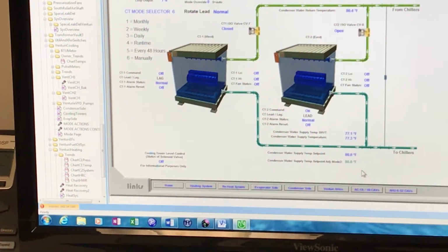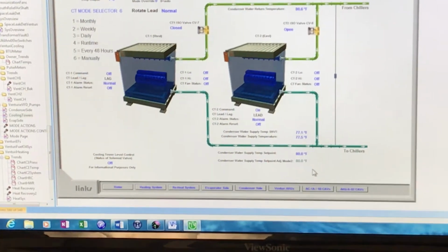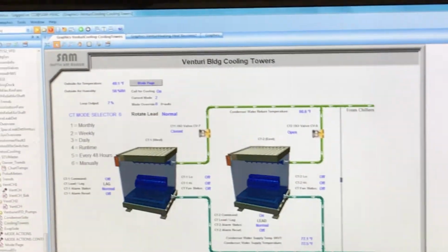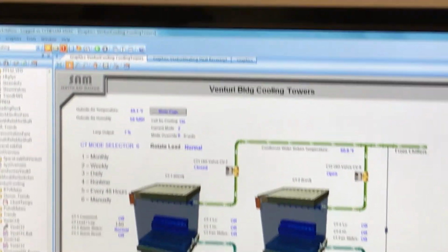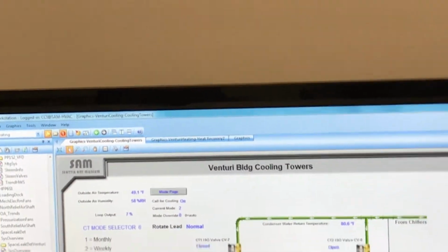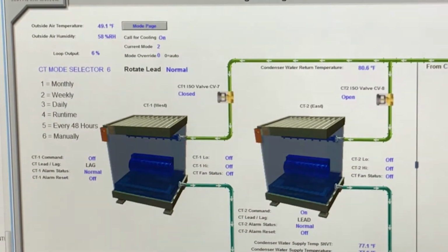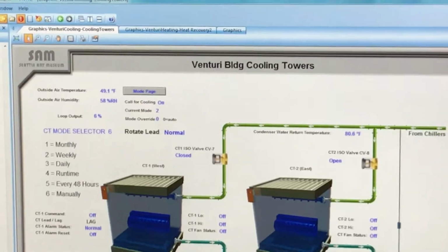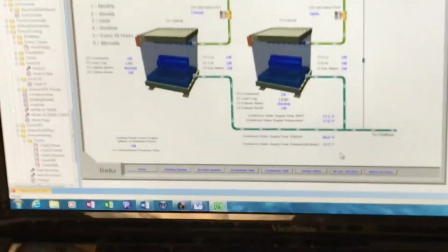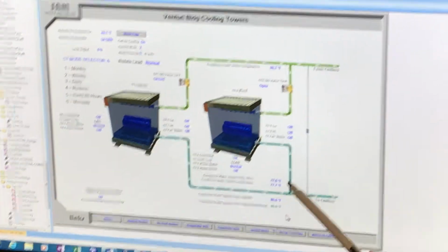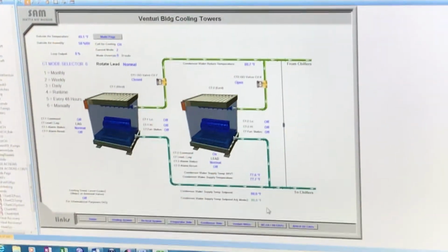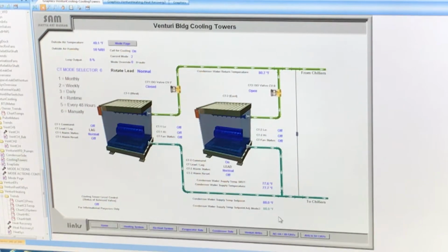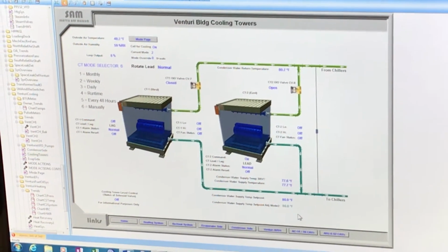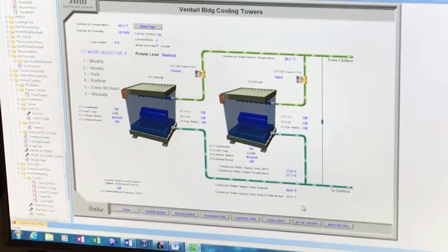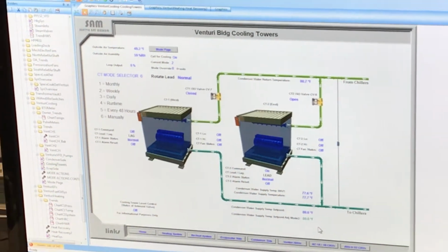So what is the loop output? That's basically the demand that the cooling tower has, like how far away it is from set point, pretty much. Okay. So if it's on set point, it's going to be 0. Like if it's 80 here, 80 here, it'll be 0. And so the further away it gets from set point, that loop tries to compensate and ramps up to 100%.